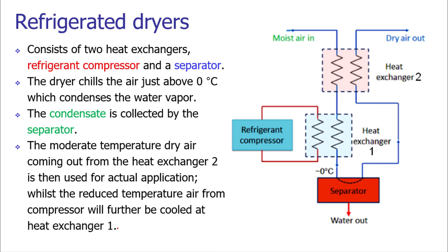We can have a variety of air dryers. Mostly we use the refrigerated dryer, which is based on the heat exchanger principle. We need to dry the air, and that cool, dry air is used for applications. In refrigerated dryers, cold air reduces the temperature of the moist air so that water particles condense. To achieve a very low temperature — say from around 80°C down to 0°C — more energy is required, so a regenerative arrangement is used to recover energy during the drying operation.